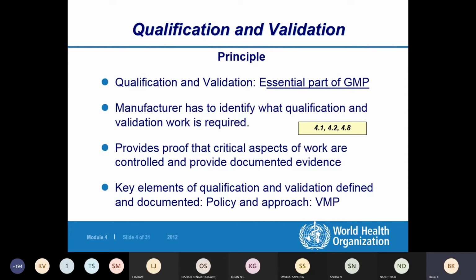The manufacturer has to identify what qualification and validation work is required. As informed, everything goes with the intended use. If I use the autoclave at 121 degrees, you have to validate it for 121 degrees. You can move it to 122 to 124 as well, because there will be a fluctuation of the temperature. It can't be the same at one point, because of the steam movement in and out there will be variation in the temperature. Your expectation is not less than 121.1. That is the autoclave requirement, right? So people will be on the safer side, and they will keep it at 122 to 124.